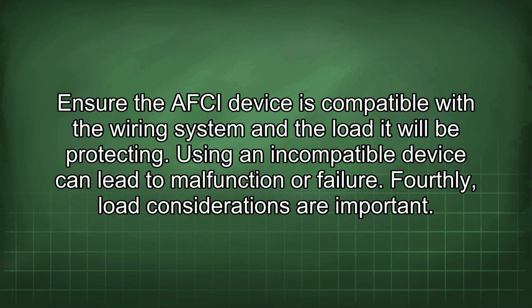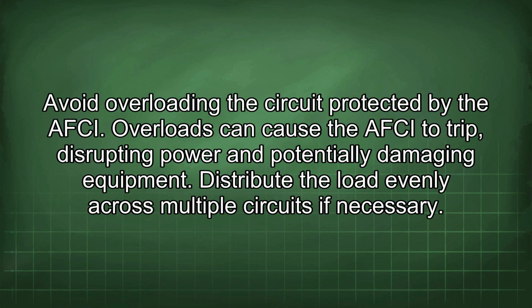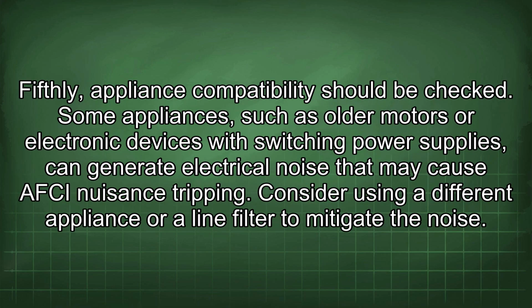Fourthly, load considerations are important. Avoid overloading the circuit protected by the AFCI. Overloads can cause the AFCI to trip, disrupting power and potentially damaging equipment. Distribute the load evenly across multiple circuits if necessary. Fifthly, appliance compatibility should be checked. Some appliances, such as older motors or electronic devices with switching power supplies, can generate electrical noise that may cause AFCI nuisance tripping. Consider using a different appliance or a line filter to mitigate the noise.